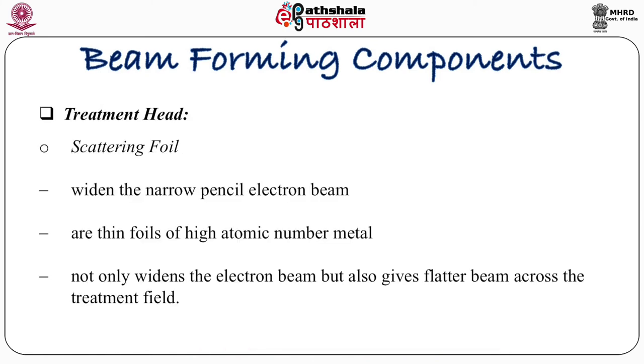The treatment head also contains a scattering foil. When we want to use photons, the flattening filter is used; but if we want electrons, a scattering foil is used. The scattering foil widens the narrow pencil electron beam. These are thin foils of high atomic number material that not only widen the electron beam but also give a flattened beam across the treatment field.